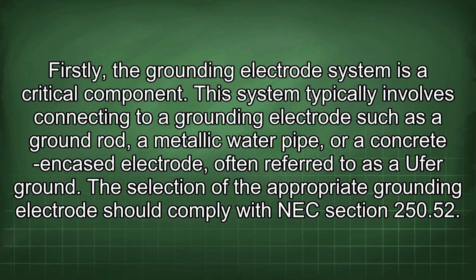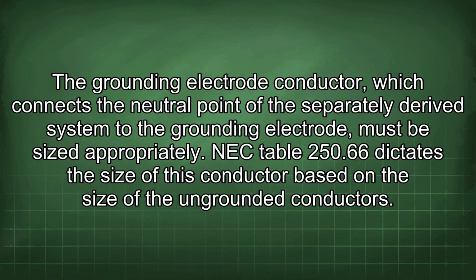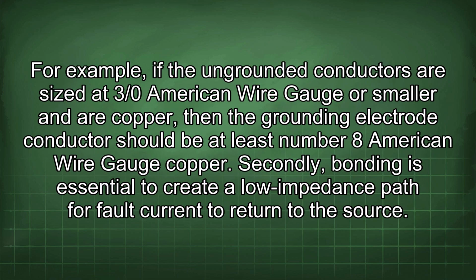The selection of the appropriate grounding electrode should comply with NEC section 250.52. The grounding electrode conductor, which connects the neutral point of the separately derived system to the grounding electrode, must be sized appropriately. NEC table 250.66 dictates the size of this conductor based on the size of the ungrounded conductors. For example, if the ungrounded conductors are sized to 3/0 American wire gauge or smaller and are copper, then the grounding electrode conductor should be at least number 8 American wire gauge copper.